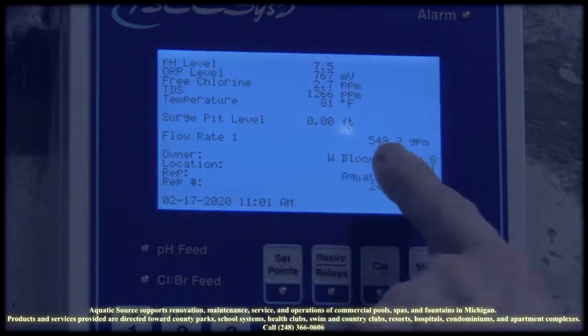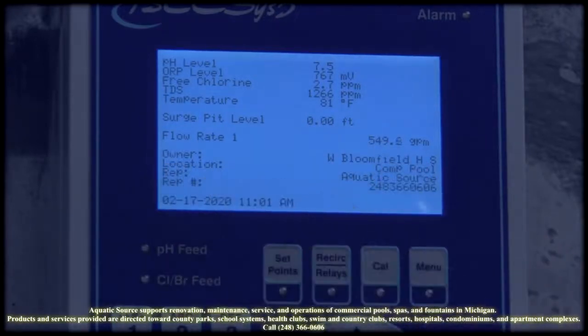On this one right here, we can control set points as to where we want to maintain the level. Here we're maintaining the pH at 7.5. We're maintaining chlorine free available at 2.5.